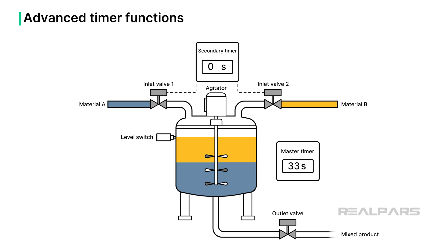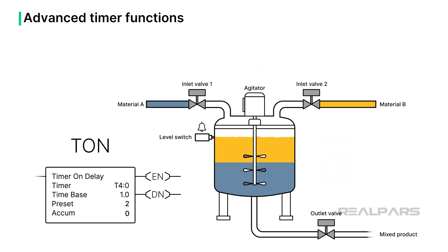Timers can be used to provide debouncing of an alarm condition. If the level in a tank is at the high level switch point, the resulting alarm may chatter, turning on and off repeatedly as the level bounces around the alarm point. If I put an on-delay timer in the logic so that the alarm condition must be present for a period of time before triggering, I can reduce the chatter in the alarm.